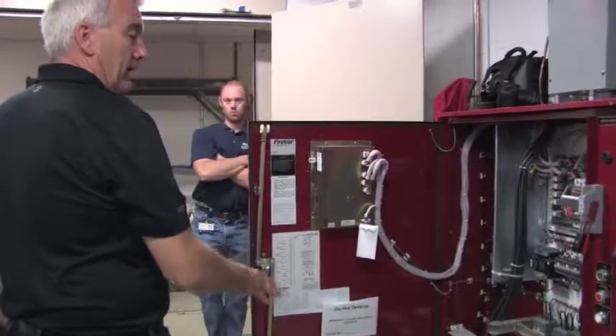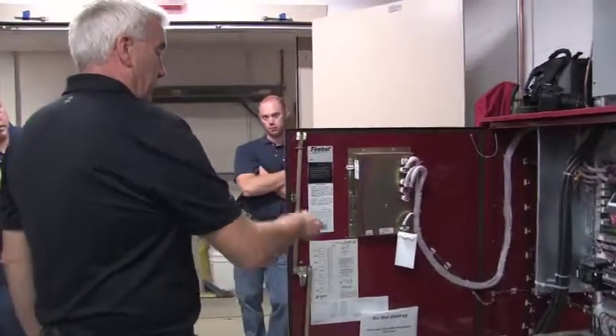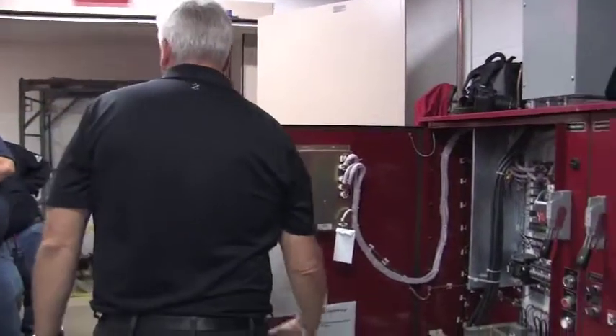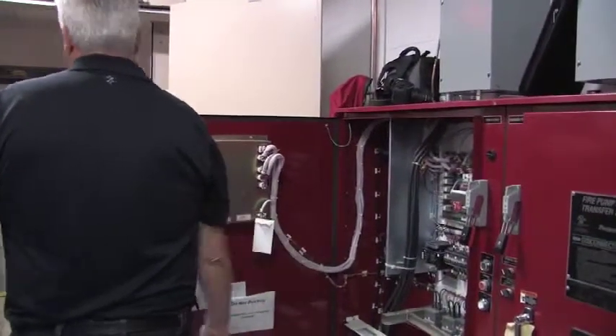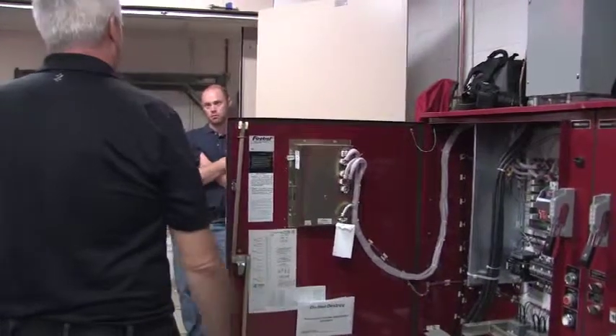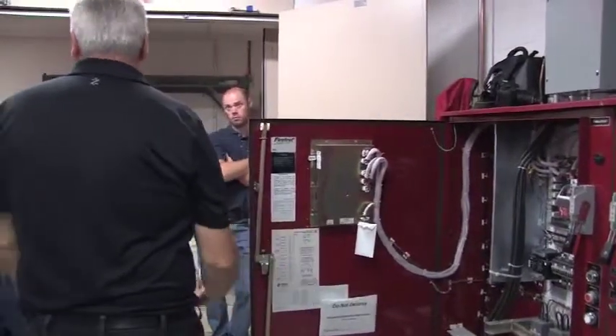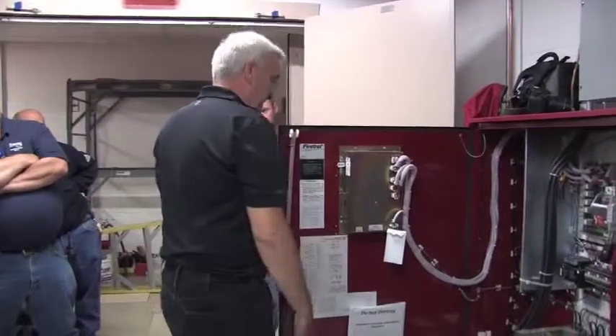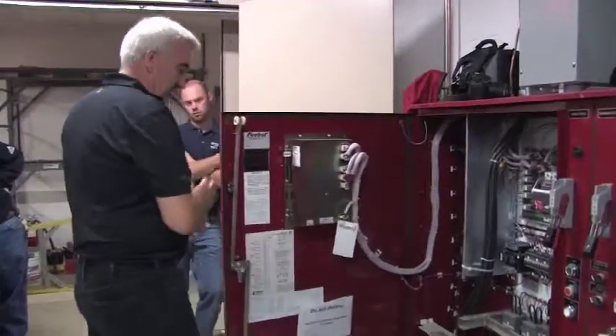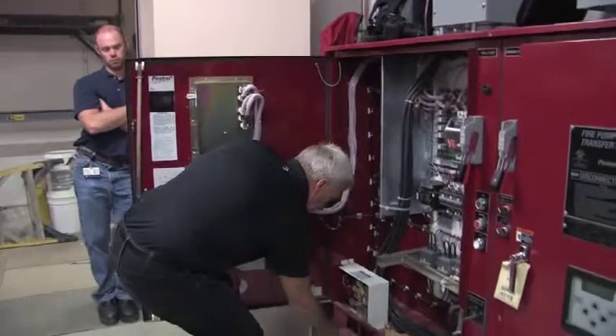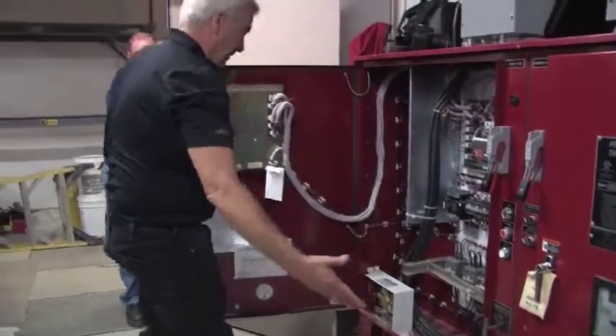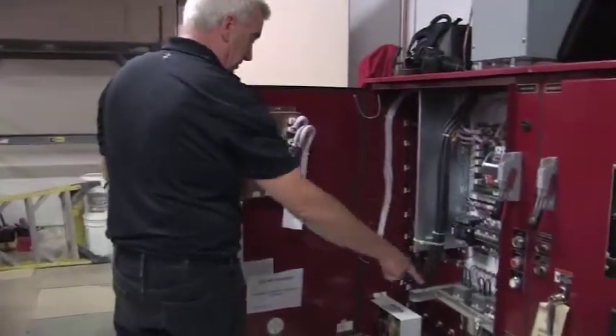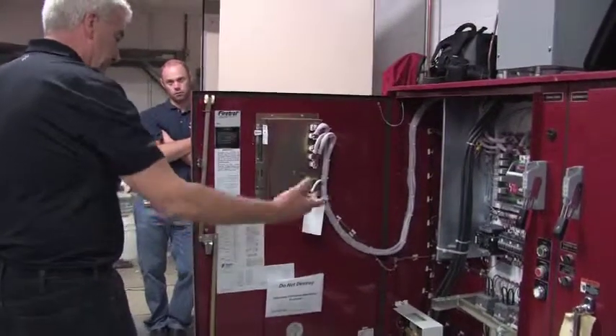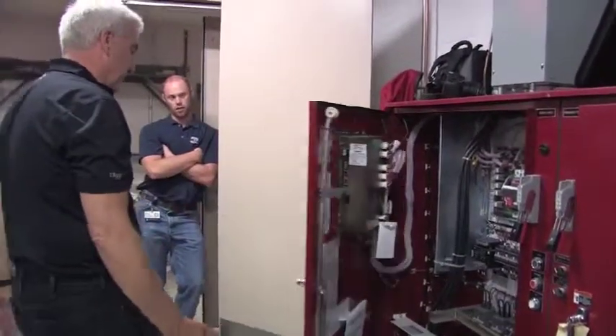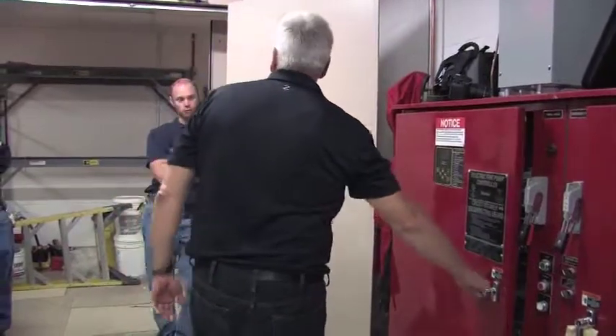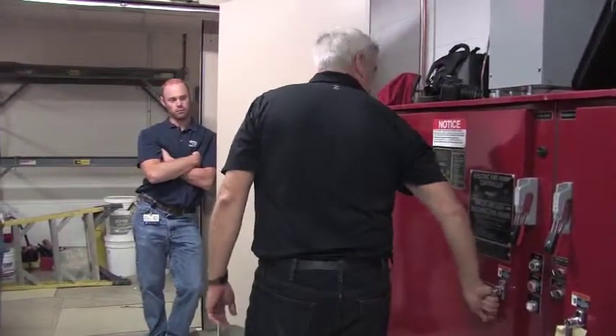What I don't like about that is all solenoid valves get clogged from time to time, especially with old sprinkler water. So a lot of times I'll get a call back saying the thing is dripping. It's just a pain in the neck. It's a maintenance issue, but it has to be there for code, okay? And this one, you don't necessarily have to pipe it anywhere, like this is just going to the floor, which is perfectly fine. But you'll see, if you hit that test button, you'll have that sprinkler pressure pumping right on the floor. So that's another reason I like to see it. So that doesn't transfer power, just. Oh, God, no, that's a controller on a pressure drop. That's all, purely a pressure drop.